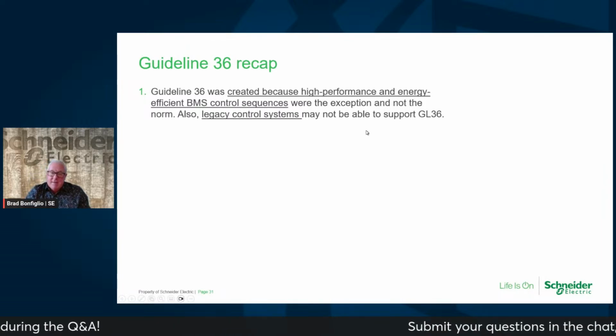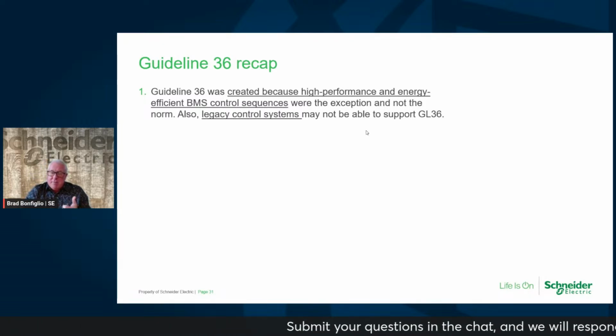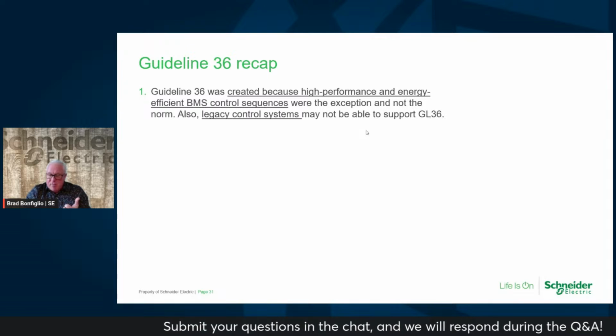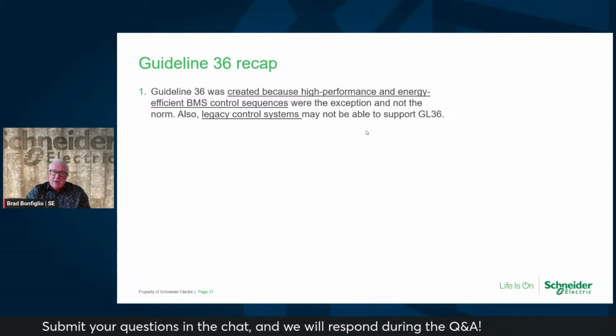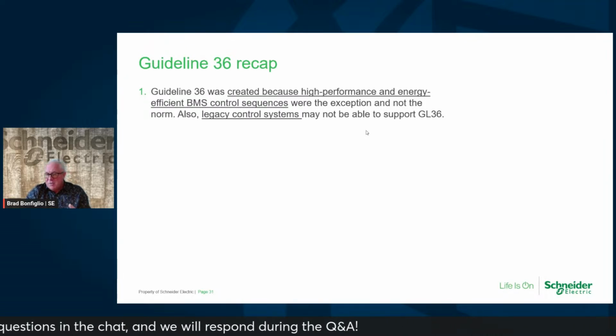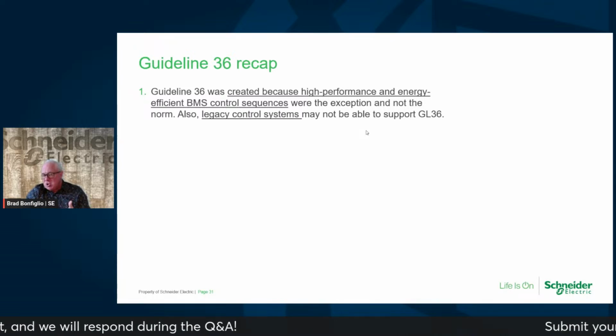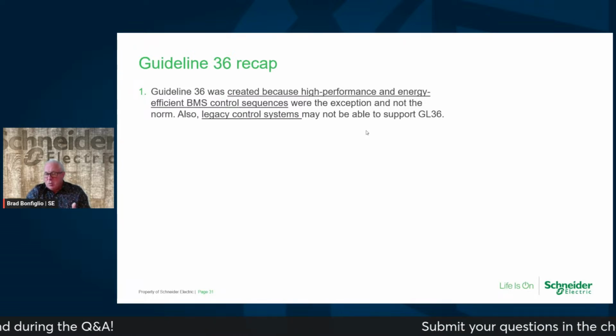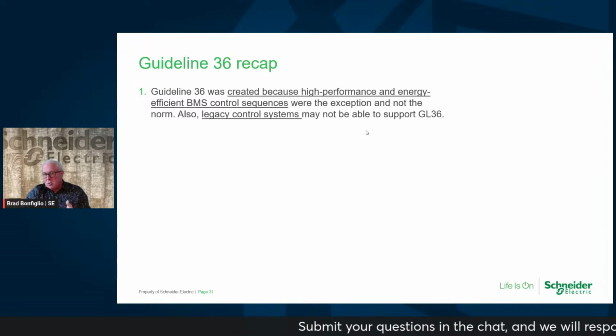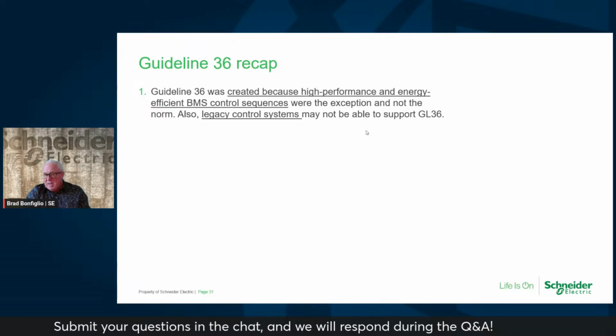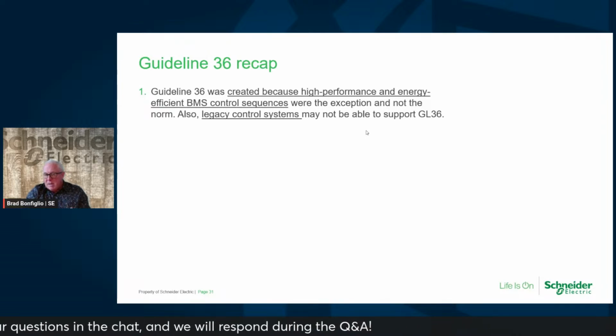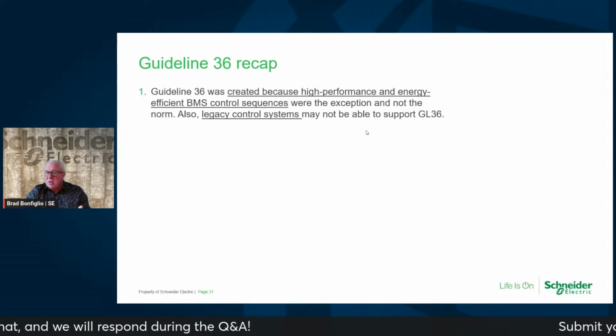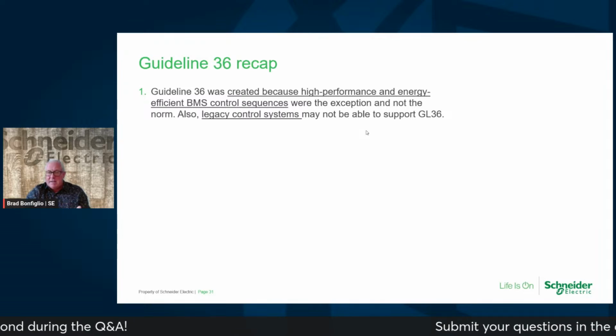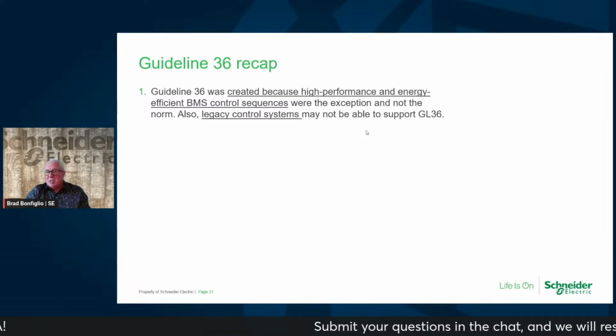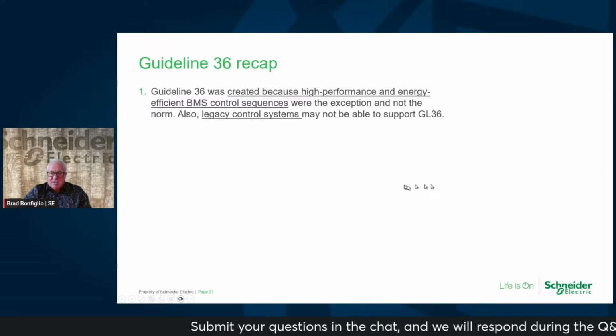That goes from an IP versus MSTP configuration on the bandwidth it's going to put on the network. That goes back to the application specific controllers versus advanced application controllers that have memory to them. So advanced application controllers typically have custom programming you can do in them. It supports COV, has local trending, alarming, has memory storage. The CPU typically with those type of controllers can handle Guideline 36. So those are all the things to think about when you've got an existing system.